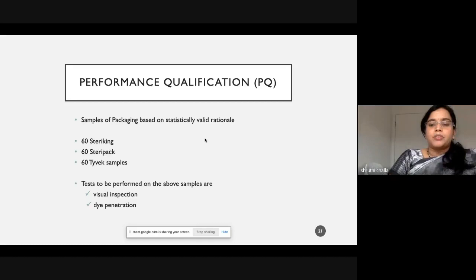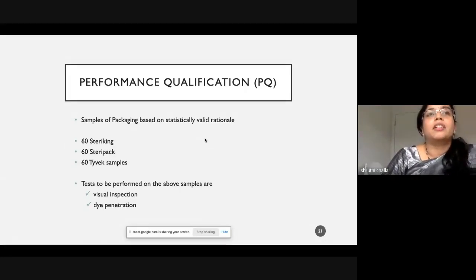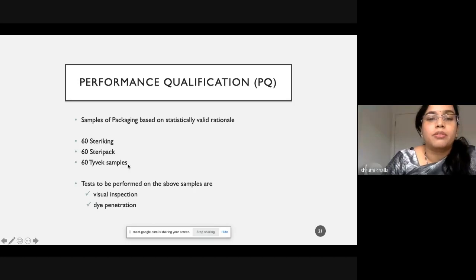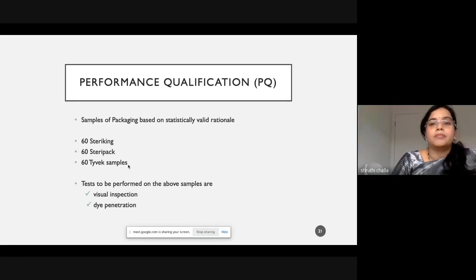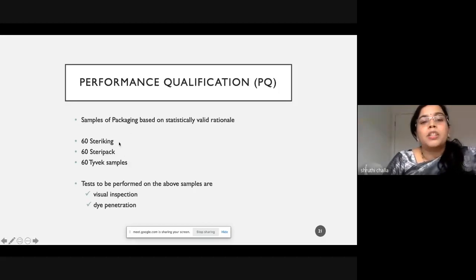So because this is such a simple equipment, as I told you before, we haven't done a separate performance qualification. We combined it with the process validation. We did have 3 different types of packaging, which we wanted to seal using the sealer: Steriking, Steripack, and Tyvek. So we need to take some samples of packaging based on a statistically valid rationale to do this performance qualification. Based on that rationale, we have taken 60 samples of each type, and we seal using the sealer, and we do the test to check whether the sealer is good or not.